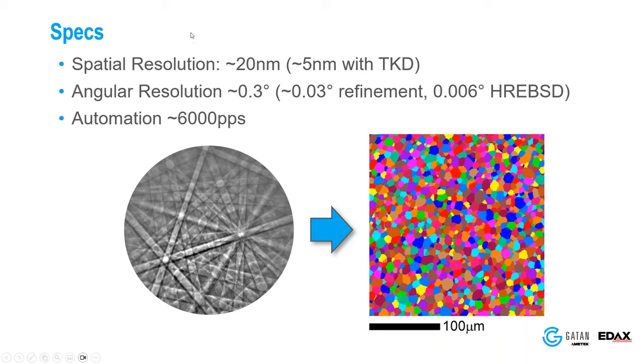The spatial resolution of EBSD is typically around 20 nanometers, depending on microscope conditions and the sample. We can get finer resolution with transmission Kikuchi diffraction. The angular resolution is typically about a third of a degree, improvable by an order of magnitude through refinement techniques, with some high-level analysis achieving two orders of magnitude improved orientation precision. As mentioned, automation now allows over 6,000 points per second, enabling us to reconstruct microstructures really well using EBSD data.